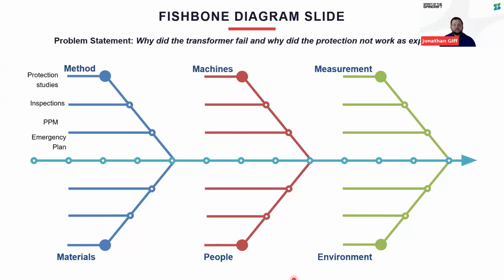Yeah, thanks, Cody. So given that the fault didn't clear where we expected it to clear on the circuit breaker protecting the transformer, and given the duration the fault was on the system for, I think Dan had said it was circa 3 seconds, the protection studies is obviously a good starting point.